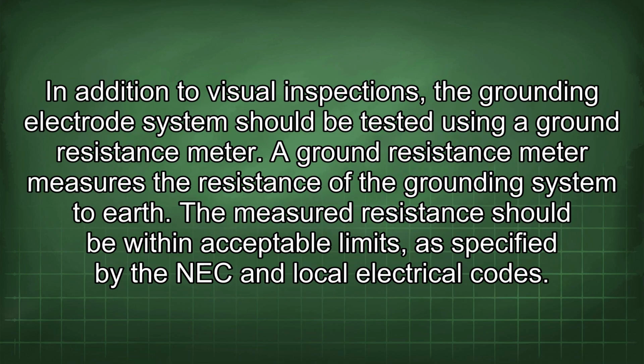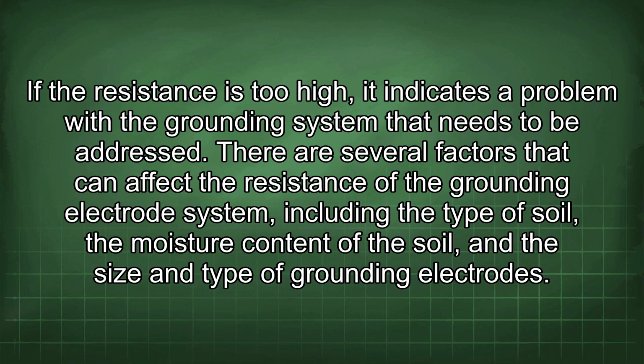In addition to visual inspections, the grounding electrode system should be tested using a ground resistance meter. A ground resistance meter measures the resistance of the grounding system to earth. The measured resistance should be within acceptable limits, as specified by the NEC and local electrical codes. If the resistance is too high, it indicates a problem with the grounding system that needs to be addressed.